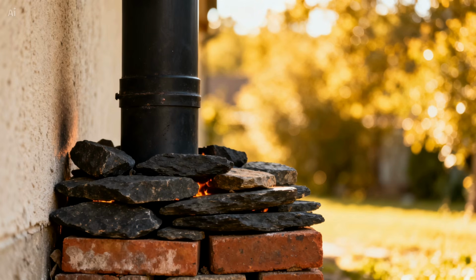For even greater performance in extremely hot climates, add a thermal mass element to the system. Stack dark-colored stone, brick, or water-filled containers against the south wall near the base of the chimney. These materials absorb solar heat during the day and release it slowly into the airstream, feeding the chimney draft, extending the ventilation effect into the early evening hours, even after the sun drops below the horizon.